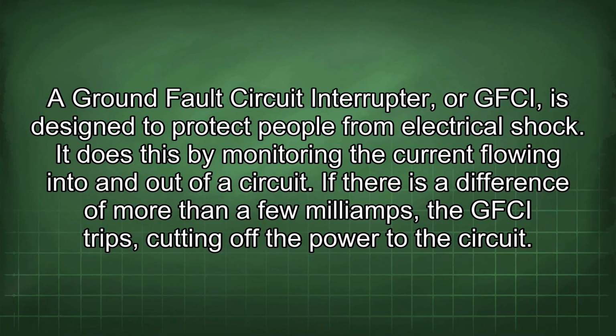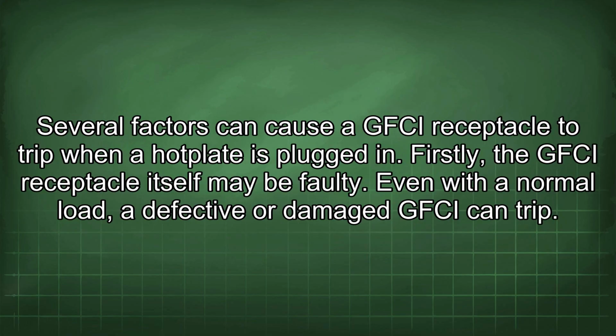Ground Fault Circuit Interrupter, or GFCI, is designed to protect people from electrical shock. It does this by monitoring the current flowing into and out of a circuit. If there is a difference of more than a few milliamps, the GFCI trips, cutting off the power to the circuit. Several factors can cause a GFCI receptacle to trip when a hot plate is plugged in.